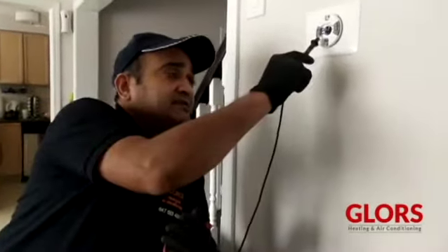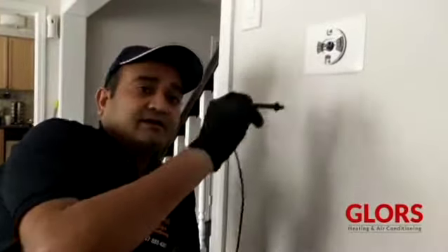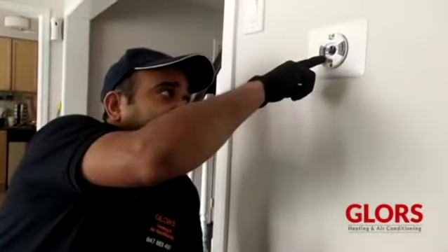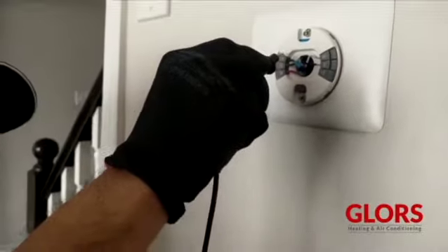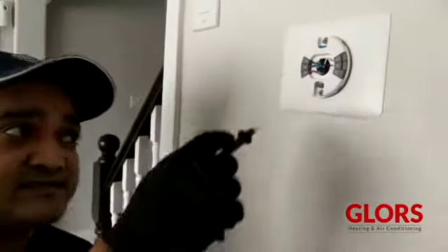So yes, we are at the customer's thermostat here. We already checked the furnace. The power is there on the R wire, which is this one, at the same point on the furnace. There are 24 volts on the R. But when you set your thermostat to the AC, that same R wire gives power to the AC call, which is Y or Y1 in some cases.